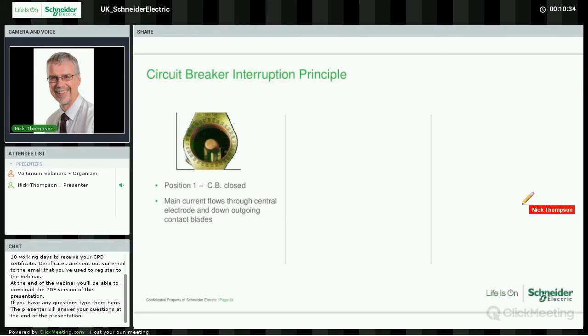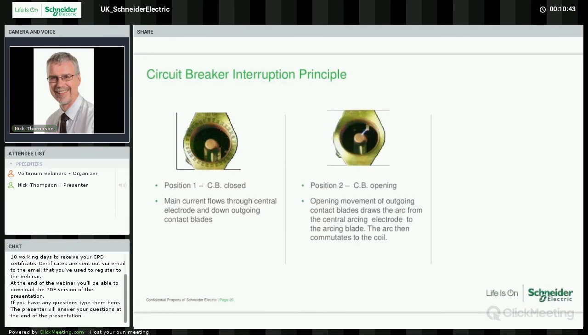Well, we've got the breaker closed and on. The blades sit at the back of the central electrode. When we interrupt the circuit or switch it off, two things happen. The blades will move very, very quickly under force from the springs that are driving the blades open, but also it will instantly strike an arc as the blades open. Once the blades are fully open and are home on the contacts behind the copper coil, the arc is then transferred to the inner edge of the copper coil.